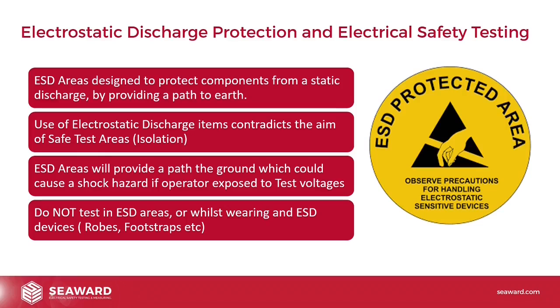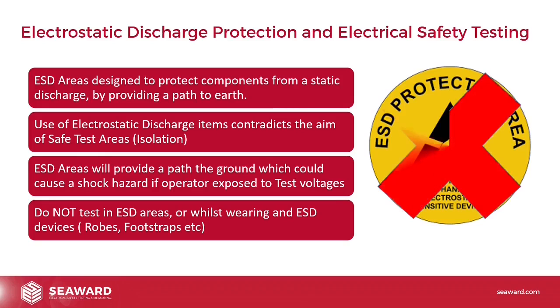We get asked a lot about electrostatic discharge protection areas. Do not use a tester in an ESD area. ESD areas are designed to protect components from static discharge by providing a path to earth. That is the opposite of what we're after here. So it totally contradicts our aim, which is isolation. So we are trying to prevent any current going from you or your equipment down to earth.